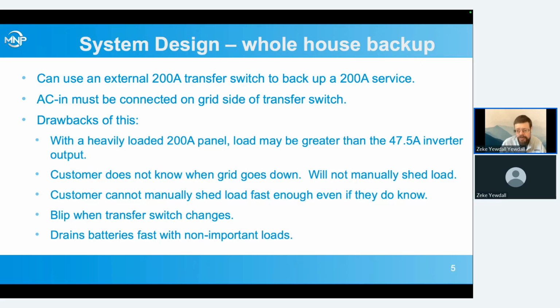If you run through the integrated transfer switch that's inside the inverter, it's fast enough that you don't have those blips that knock all the computers and everything offline. So that's a disadvantage of using an external transfer switch.